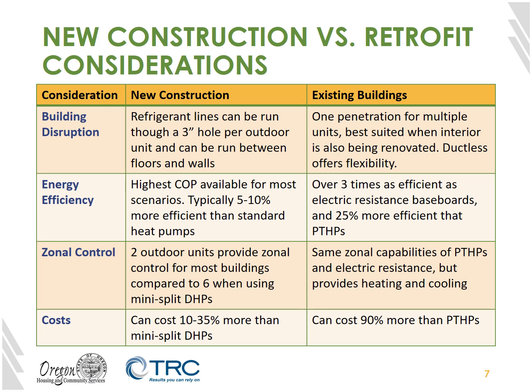And it's a bit of a labyrinth of codes and standards, but there are codes and standards specifically designed to protect both the installers and the occupants of buildings from any potential future refrigerant leak. And these are things that shouldn't scare anyone off from considering VRF, but should absolutely be considered. There will be safety considerations and cost considerations on the front end of doing this. On the other side, the benefits: you will have better zonal control, fewer building penetrations, and higher efficiency systems.